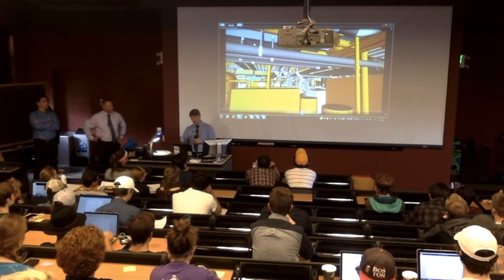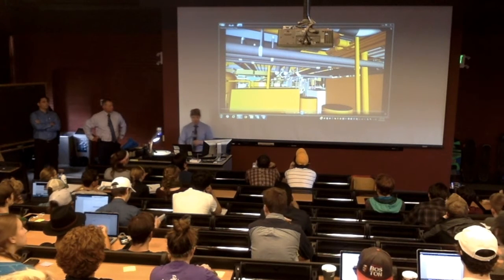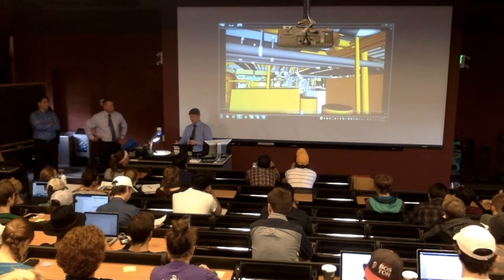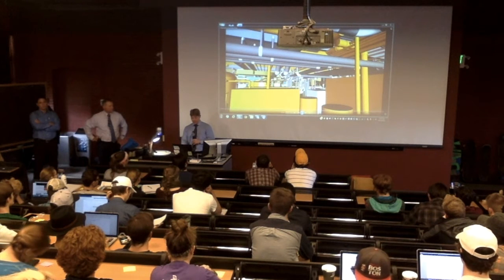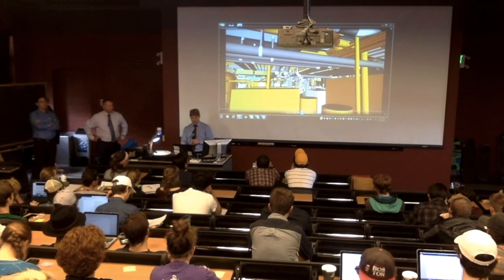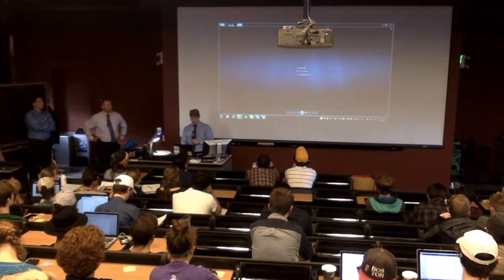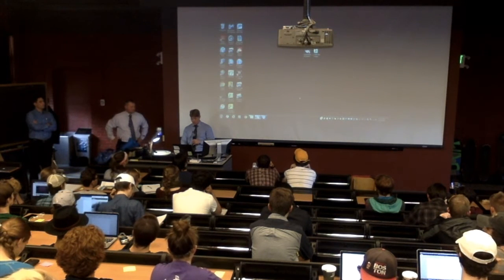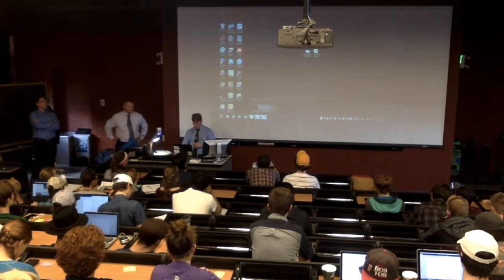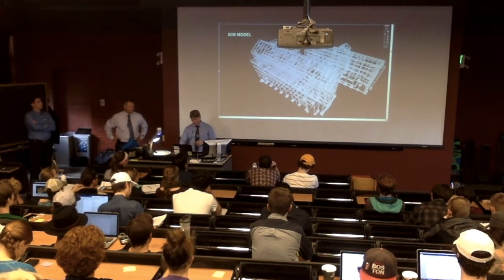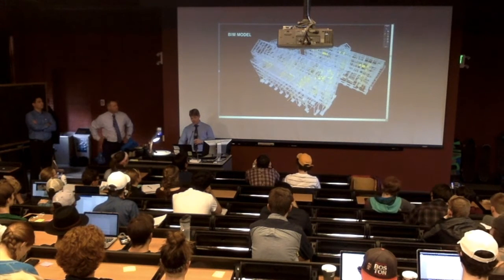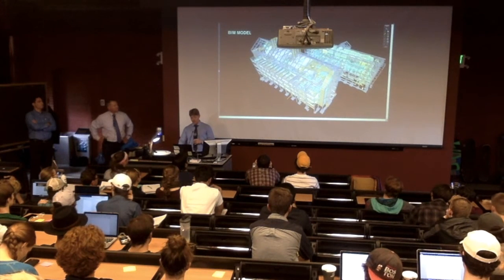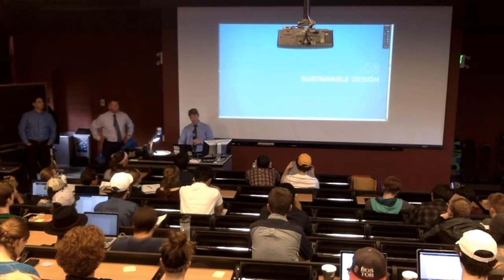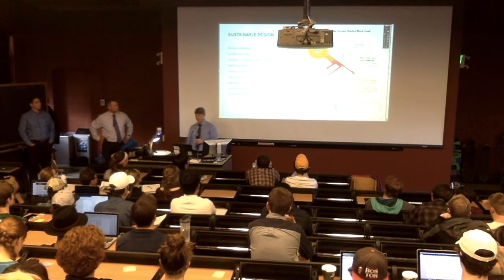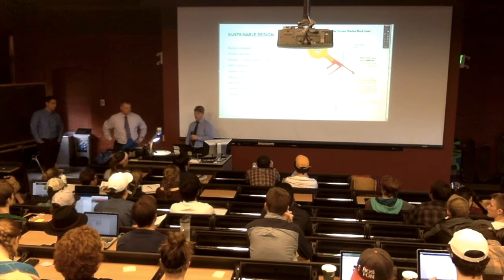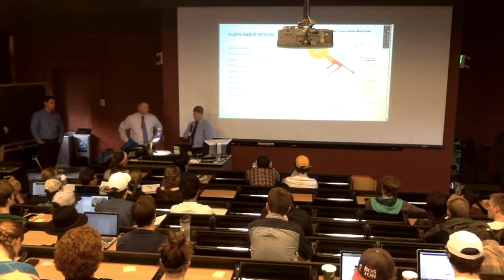And then beyond that, there's a multitude of mechanical heating and cooling pumps and heat exchangers that all need to be sized based on specific loads. Because, this day and age, you don't want to oversize things because there are energy codes, and we want to make sure things operate in their sweet spot to reduce the energy use. So you can see that's kind of a snapshot of what we produce as far as documents. And then we'll get back to the slideshow right now. Again, just going through the structure, electrical, plumbing, fire protection, and the HVAC systems. And all that stuff really, like I was saying, needs to be sustainable. So I'll turn it over to Al to kind of cover a few of the major topics that both architecturally and mechanically we need to address.